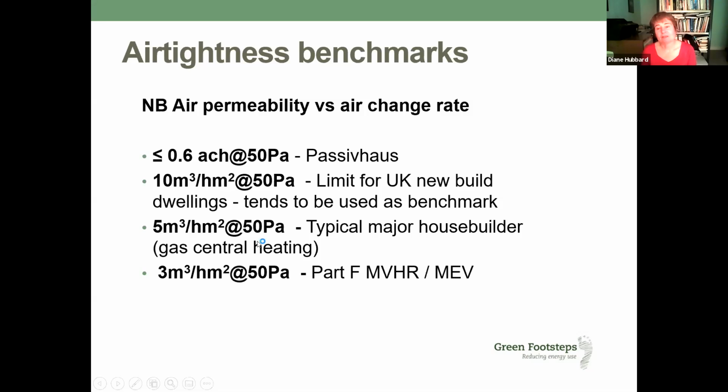What you find more commonly is that buildings have to achieve a standard somewhere between about 3 and 8. This is for new builds, in order to pass building regs. And a typical estate type, 3-4 bed detached would usually be working to a requirement of having to achieve about 5 as a maximum. So a figure up to 5, typically between about 4.5 and 5, is what's normally achieved.